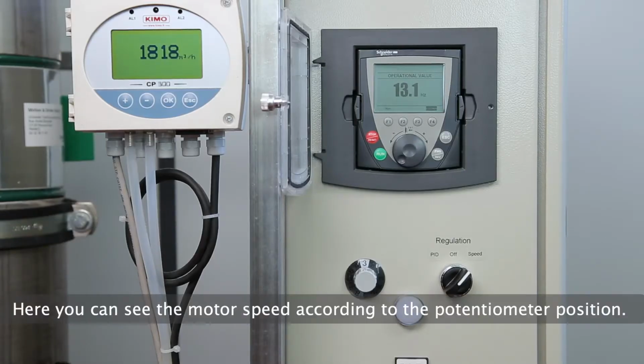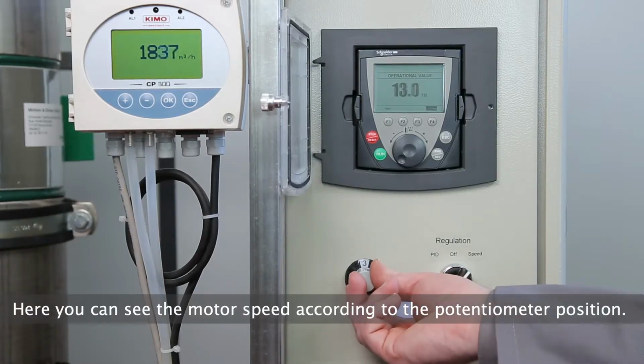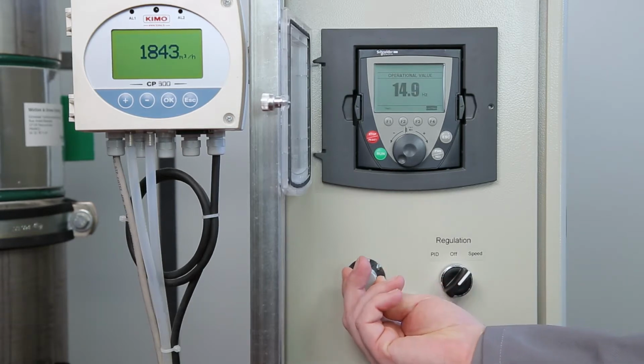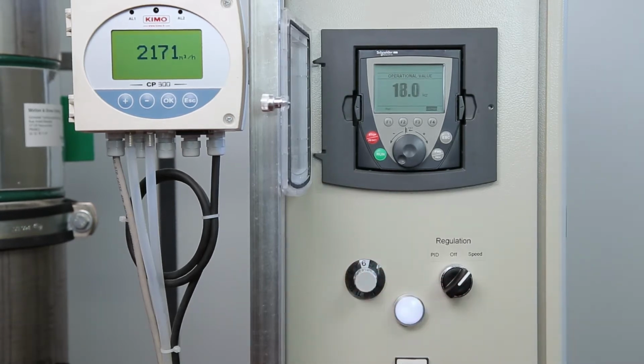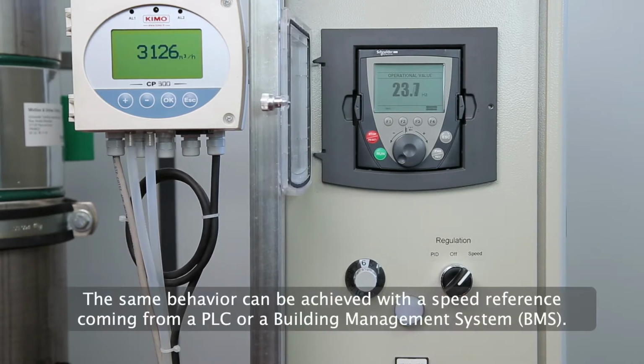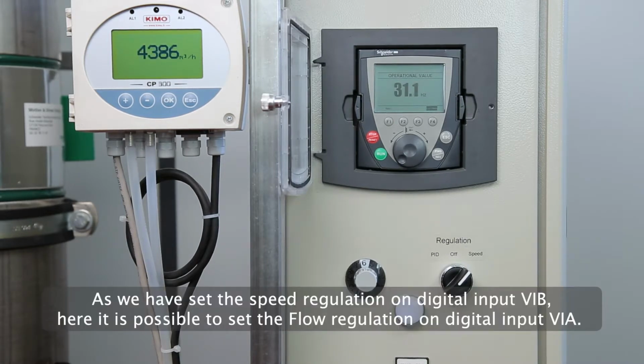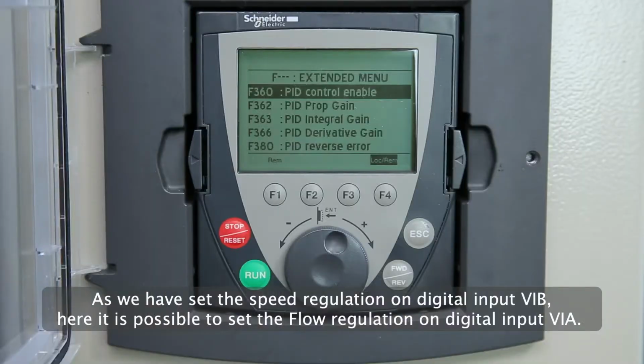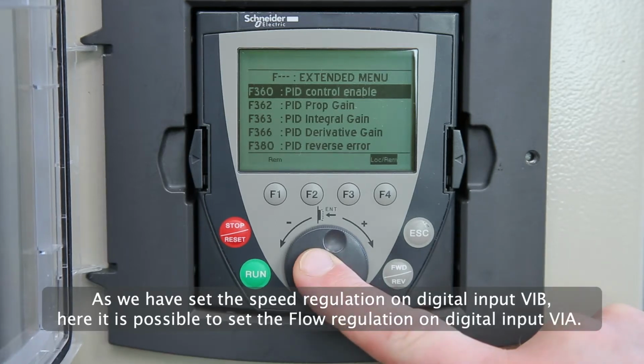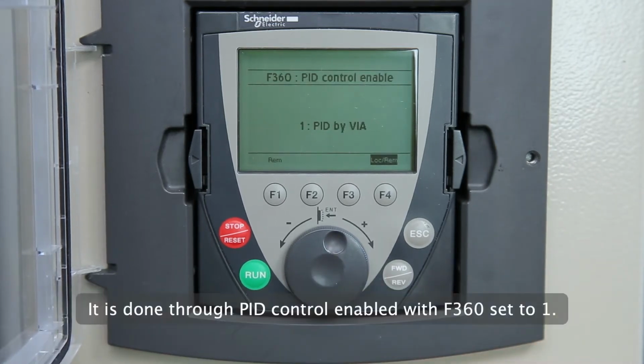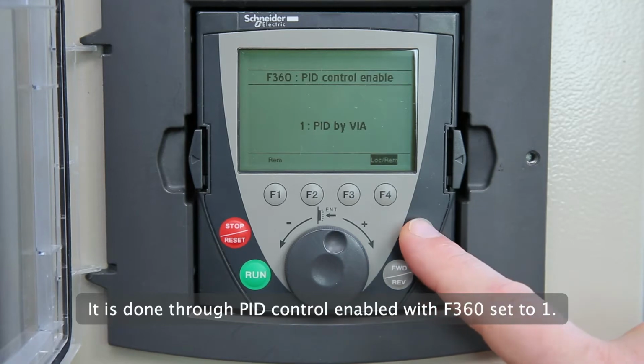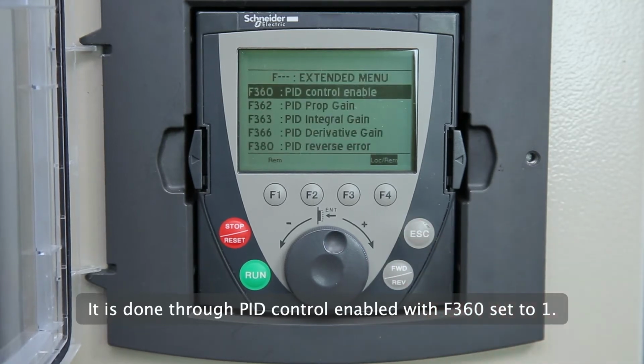Here, you can see the motor speed according to the potentiometer position. The same behavior can be achieved with a speed reference coming from a PLC or a building management system. As we have set the speed regulation on analog input VIB, here it is possible to set the flow regulation on analog input VIA. It is done through PID control, enabled with F360 set to 1.